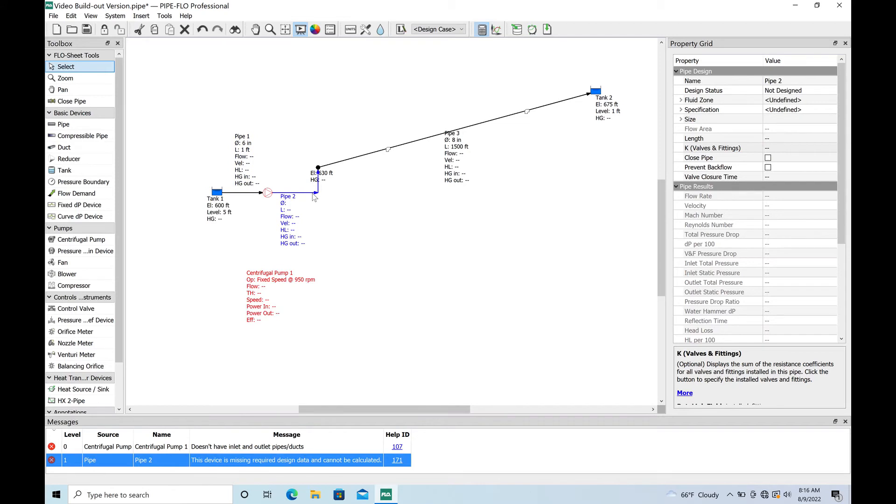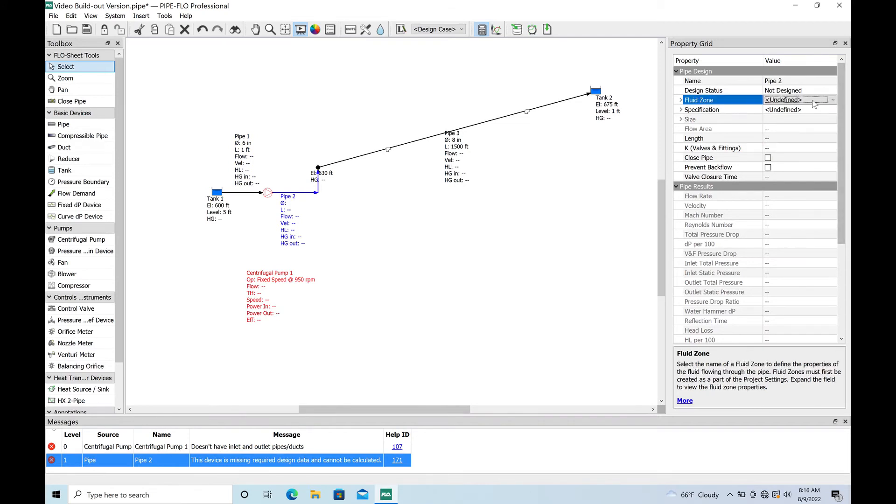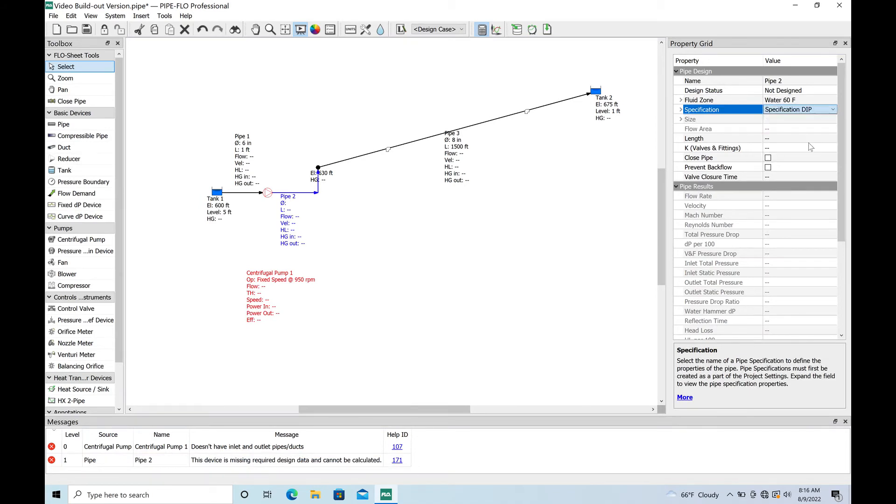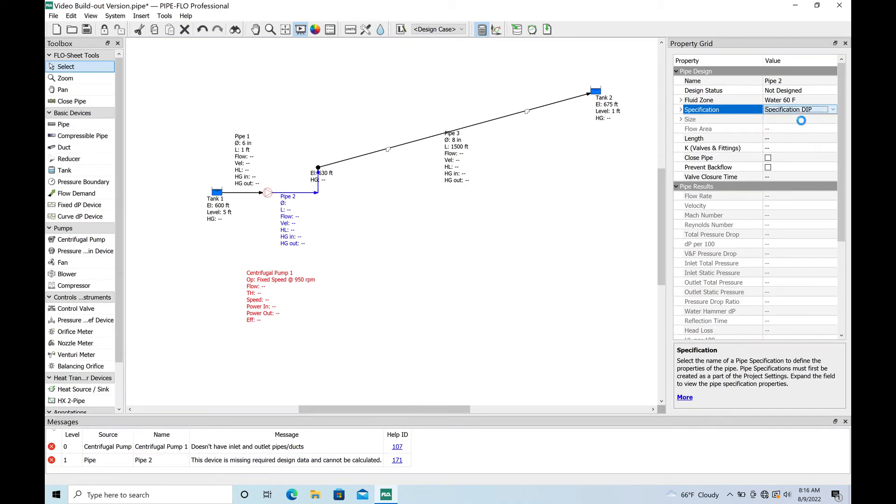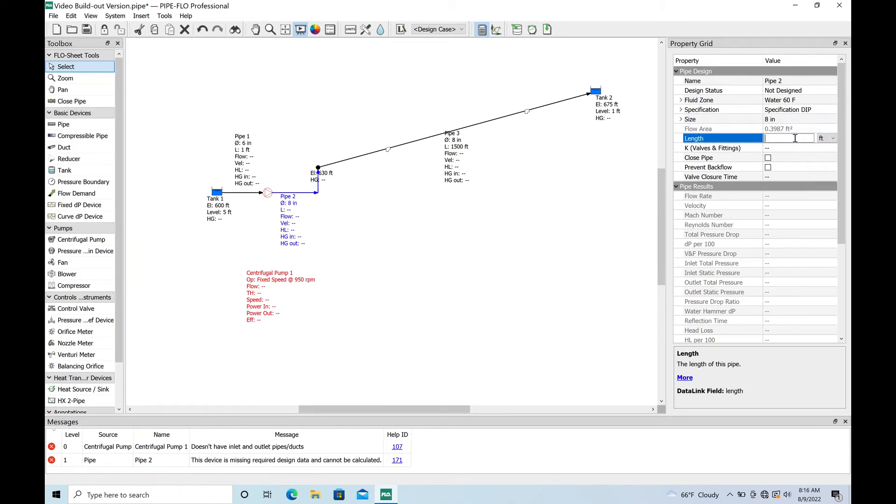We'll go ahead and enter this. This is probably the most fun part, has the most information to enter. Water again. We'll go ahead and use ductile iron pipe here and we'll say, I don't know, eight inch to match the force main, try to cut down the head loss. You'll see that it doesn't make a huge difference. We'll go ahead and make this 40 feet long. Let's say we've got a little bit of a run and we've got to get out of the ground anyway.